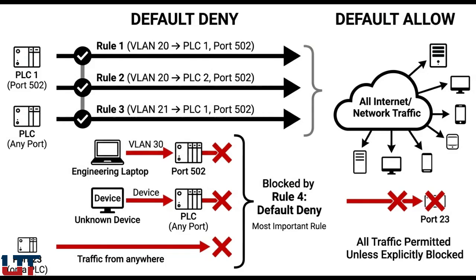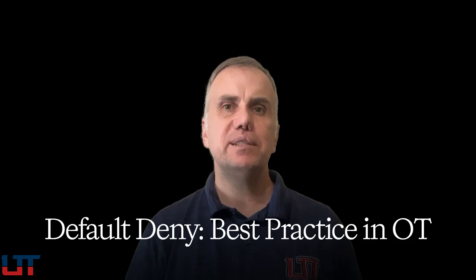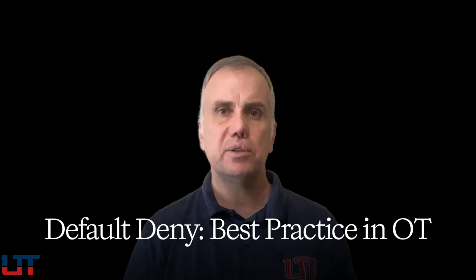Default allow means all traffic is permitted unless a rule explicitly blocks it. You write deny rules for the things you don't want, and anything without a deny rule goes through. Default deny means all traffic is blocked unless a rule explicitly permits it. You write permit rules for the things that are allowed, and anything without a permit rule is blocked. In an OT environment, default deny is the best approach, and here's why.